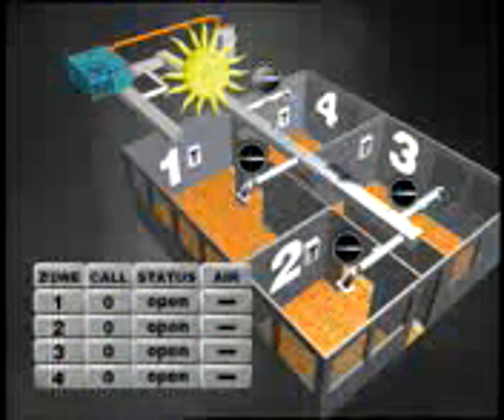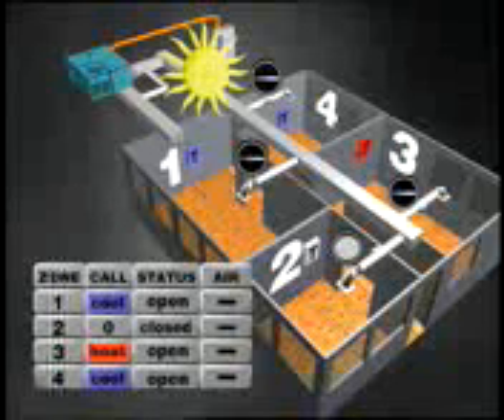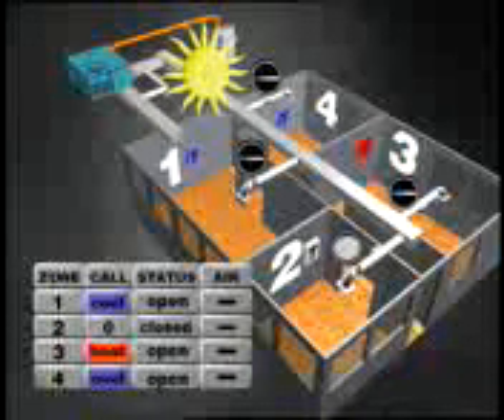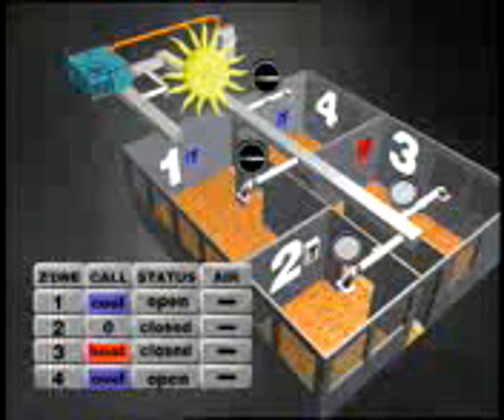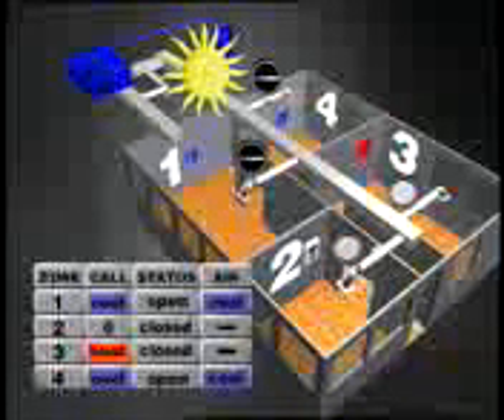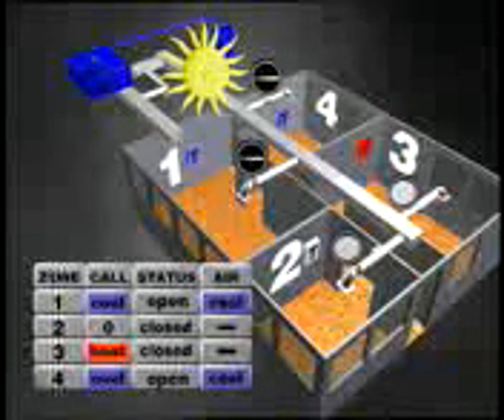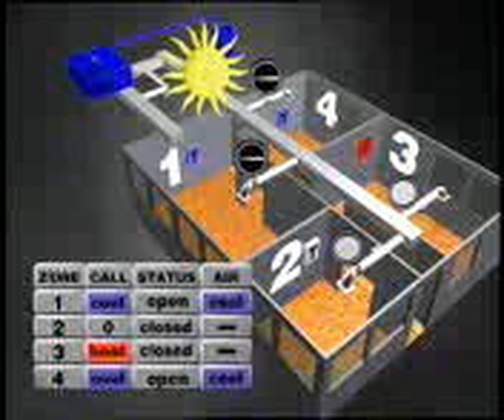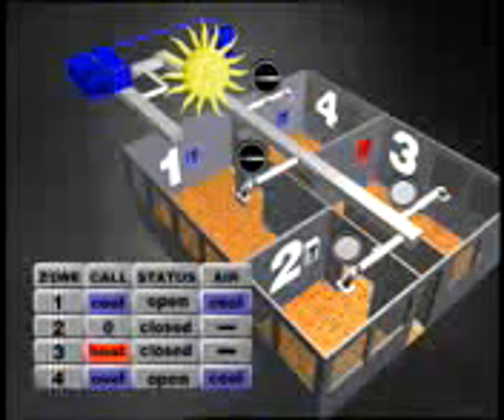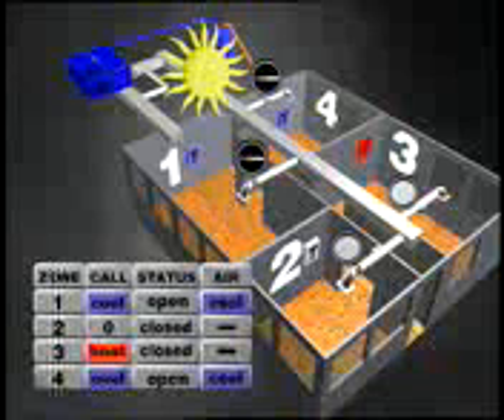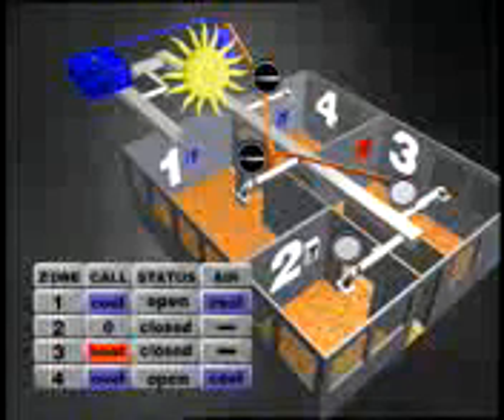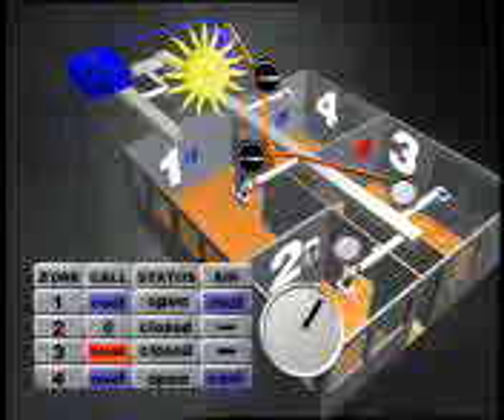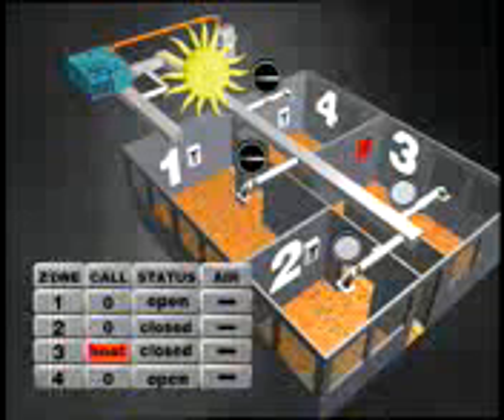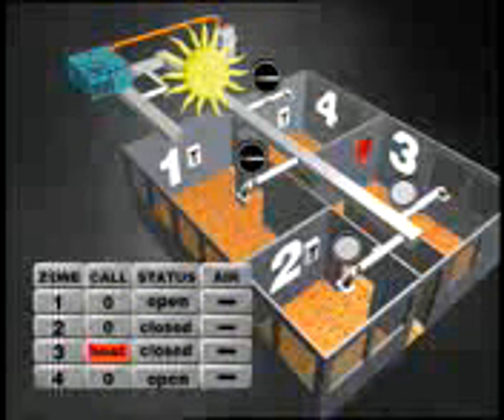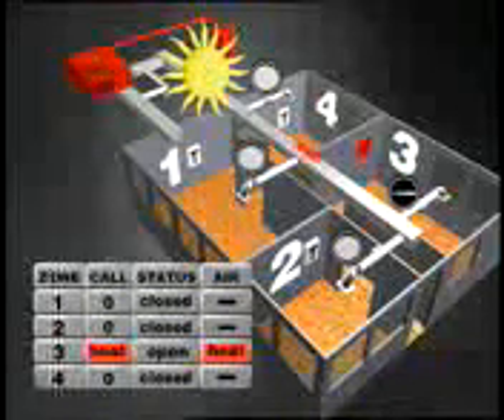Areas calling for cooling, zones 1 and 4, open. Zones requiring heat or satisfied zones, drive closed. The controller energizes the compressor and brings the system online. Zones 2 and 3 drive closed, while cool air is delivered to zones 1 and 4. After zones 1 and 4 are cooled, the controller can again check zone 3. If it is not satisfied after a built-in time delay, the system can once again change over to the heating mode for zone 3, closing off zones 1, 2, and 4.